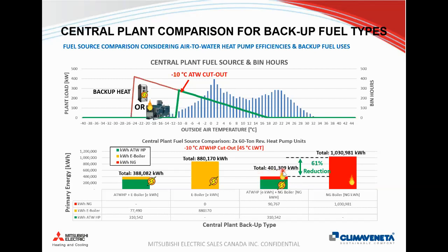Now, this is just a high-level bin hour analysis, so it doesn't take into account the staging of the heat pumps or when the units are going into defrost. This is really just intended to provide a relative comparison of the total amount of energy based off the bin hour distribution. But even if we compare a gas system to an air-to-water heat pump with supplemental gas, we can have a significant reduction of our total energy used.